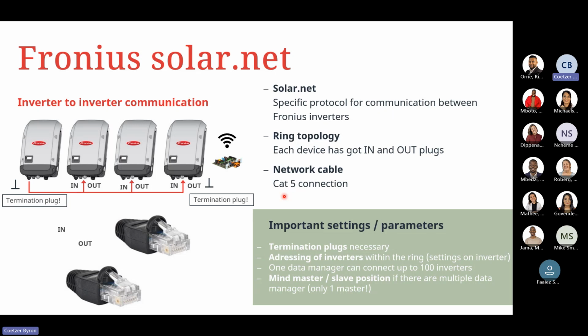So again, for your Fronius Solar Net, the Solar Net refers to how you communicate from inverter to inverter when only using the Snap inverter range. So this allows us to do Eco to a Symo 20, for example. So it's 3-phase to 3-phase. We can then do communication with one master being the device that has the data manager card. And then we can have a simple RJ45 UTP cable connection between the two units. So we'll go from out to in, and then from out to in, for example, and we'll follow the train like such for the communication side.